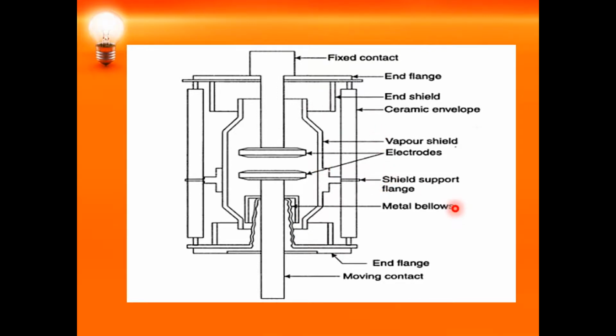Whenever a fault occurs, the contacts have to get separated. When the contacts get separated, first an arc is formed between the fixed contact and the moving contact. When an arc is developed between them, the temperature will obviously be high, which leads to ionization of the particles present there. Due to the ionization, the space will be filled with the vapor of positive ions, which are discharged from the electrodes.